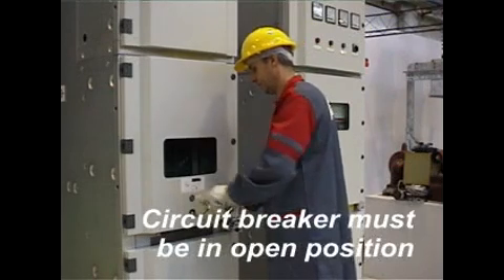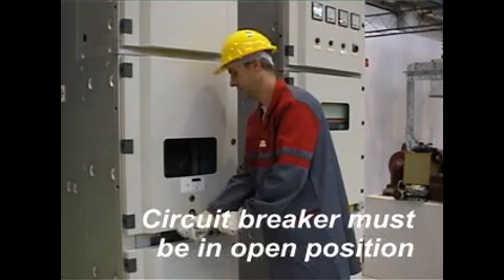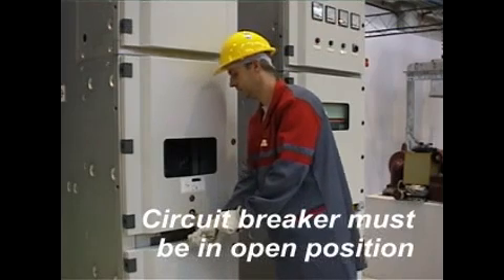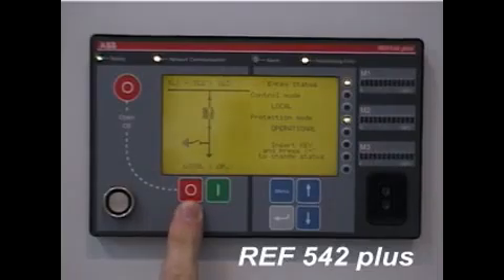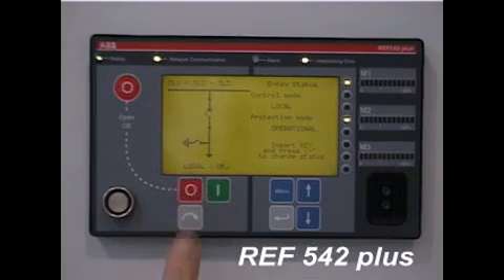The operator cannot withdraw the breaker. In fact, if you give a closer look through the window, we can see that the circuit breaker is inserted but in closed position. Therefore, we need to trip it by means of the REF542+. The screen of the REF542+ now shows that the circuit breaker is inserted and open, as confirmed by this quick view through the door.